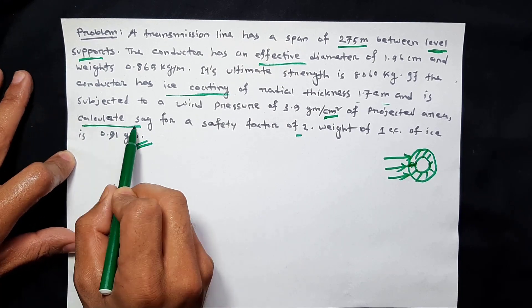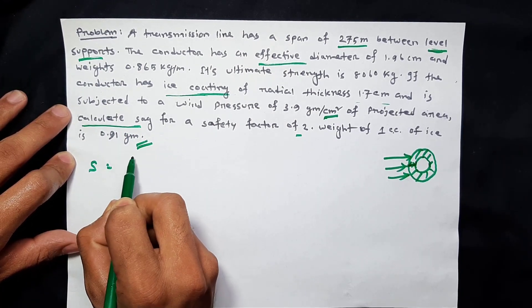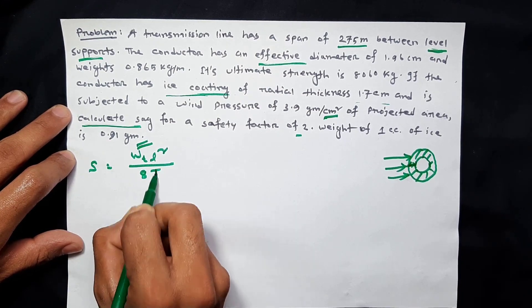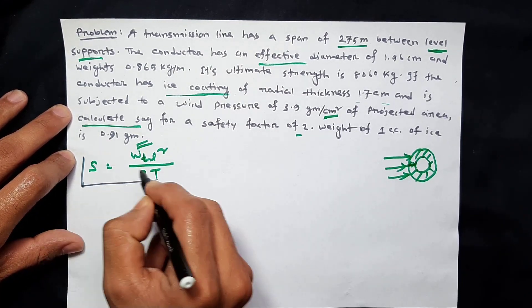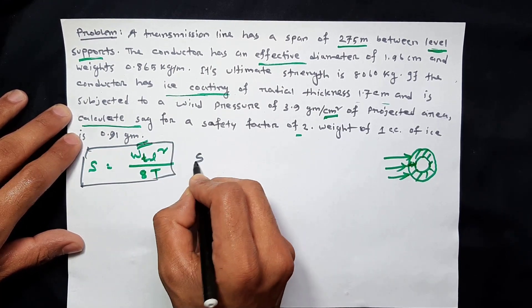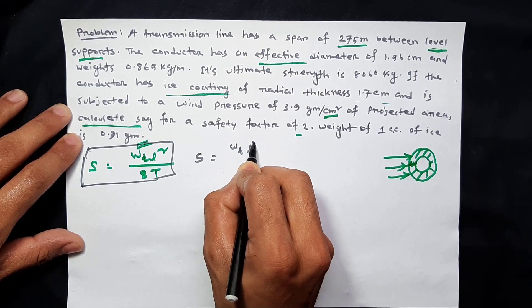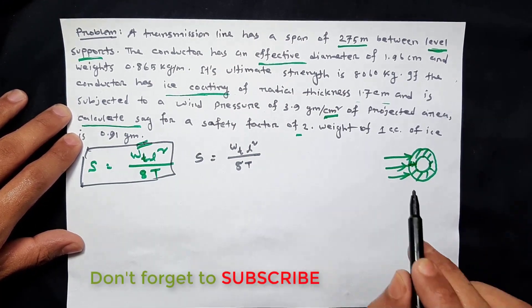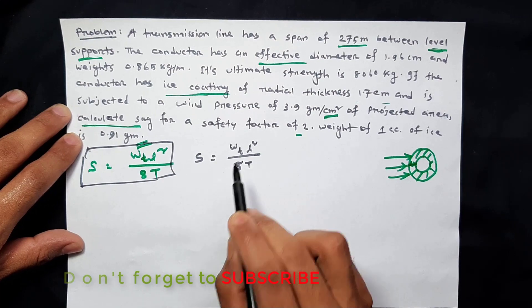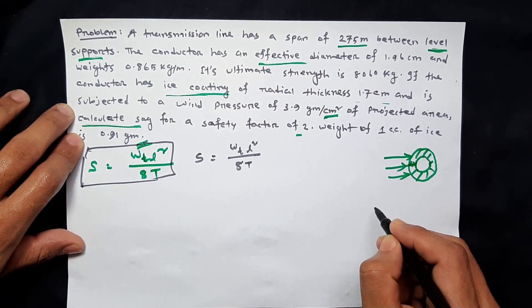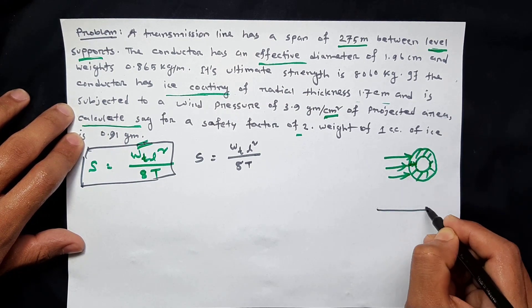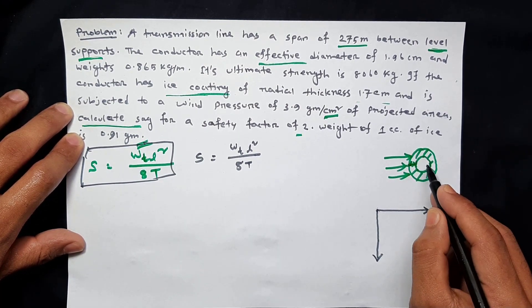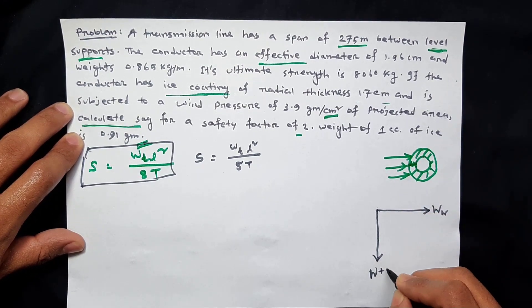Sag S is equal to Wt·L² divided by 8T. That means S equals Wt·L² divided by 8T. Here Wt is the total weight, which is the resultant of the conductor weight combined with wind and ice loading. That means resultant Wt.